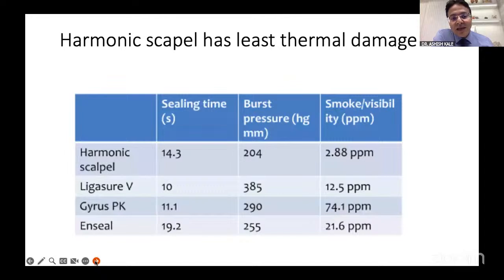So if you are thinking of the harmonic scalpel, the sealing time is 14 seconds, as compared to the LigaSure, which is 10, and the Enseal, which is 19, because the Enseal requires a longer pressure effect. The harmonic takes a little less, because it causes the pressure as well as the sealing, and it has the vibration mode, so it causes the sealing effect in a lesser time frame. When you're thinking of the burst pressure, with the harmonic it is 204 millimeters of mercury, the LigaSure is 385, and with the Enseal, it's 255.